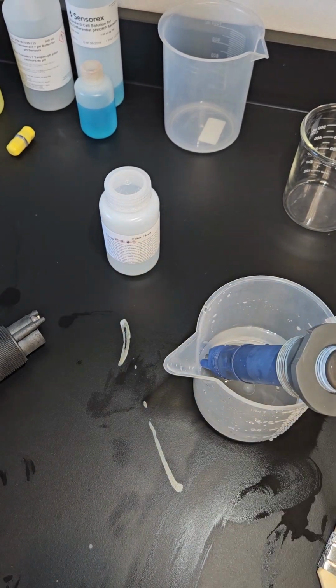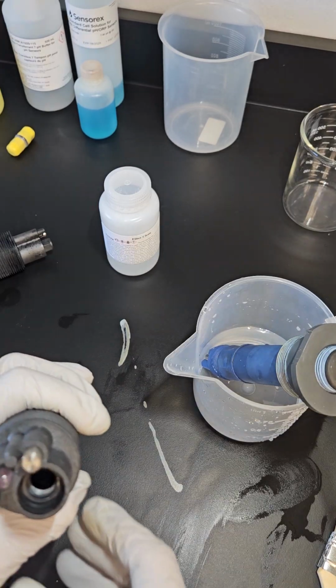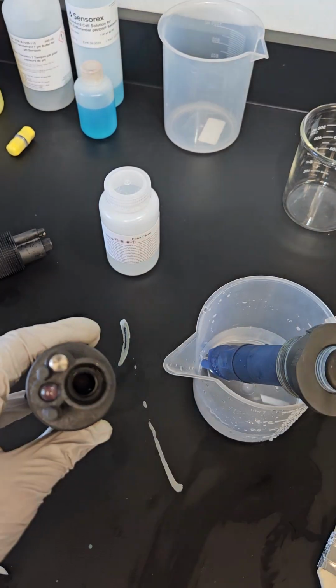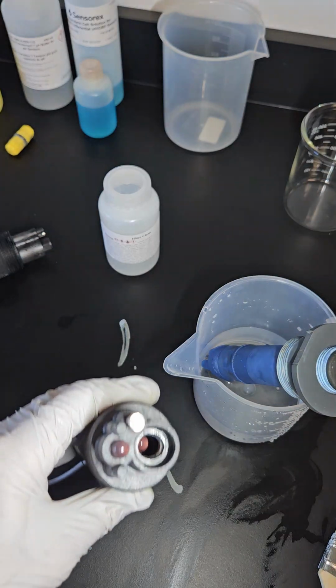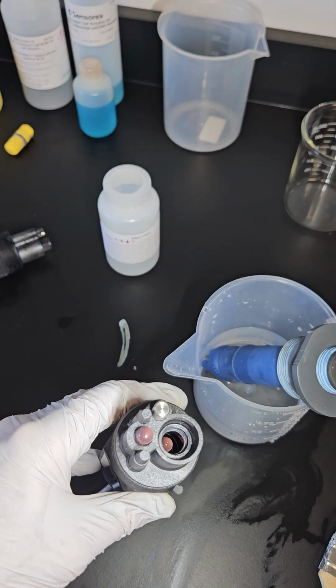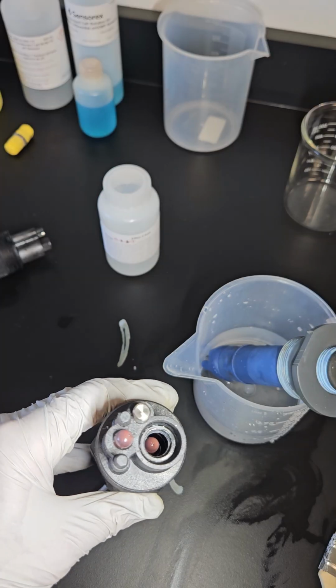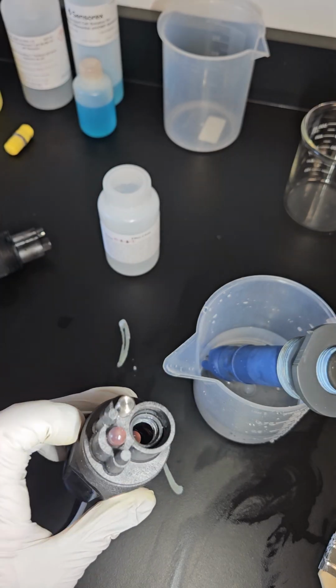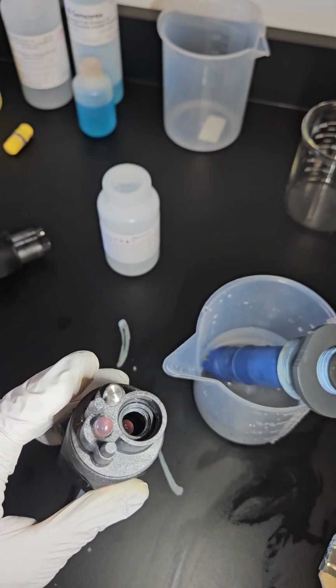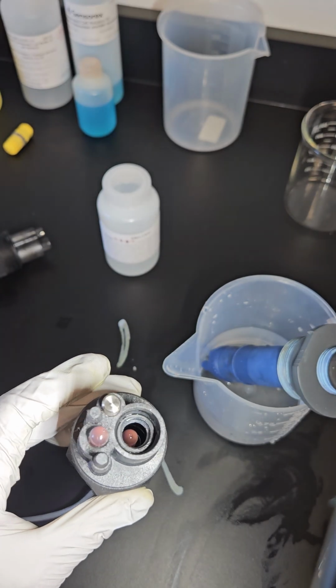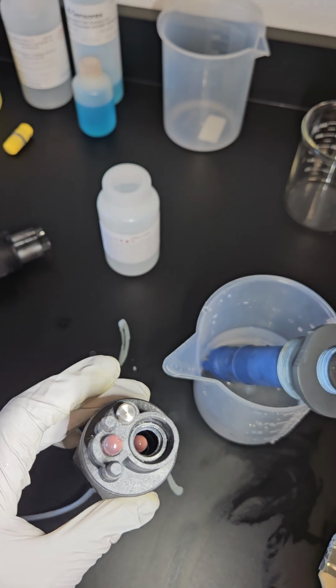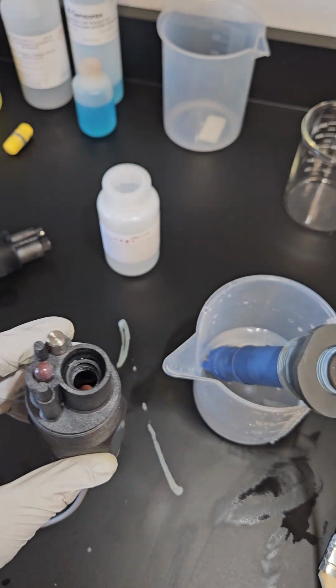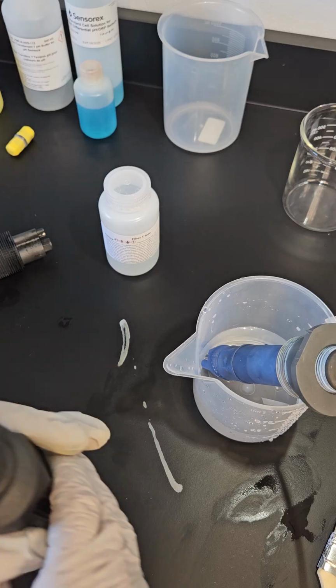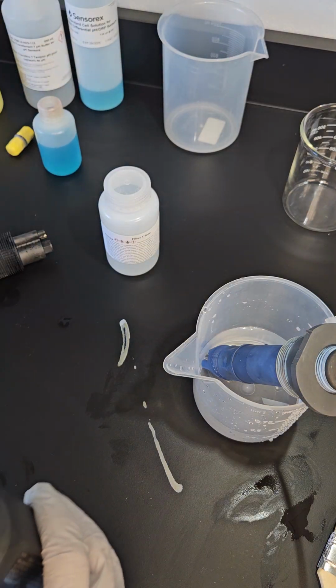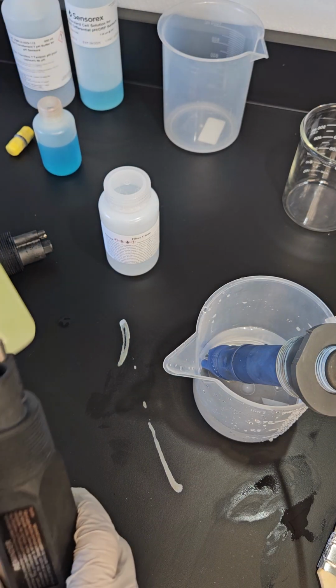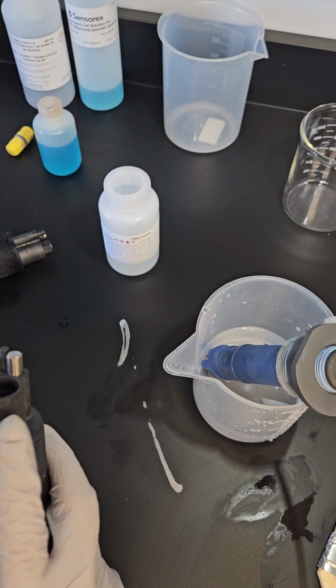So here's one probe I have ready to go. The salt bridge can actually be seen in the bottom of that capsule, or in that cavity down there. You can see a second bulb down below. So there's the primary one up here on top with its ground lug, and then the other electrode, basically the comparison electrode, is down in that cavity. I want to stress that there are different solutions out there. Some companies, in a pinch, you can use pH buffer 7 inside here. It's not really recommended, though.